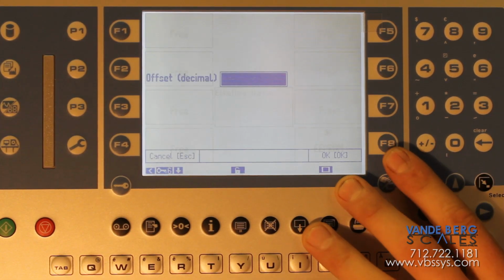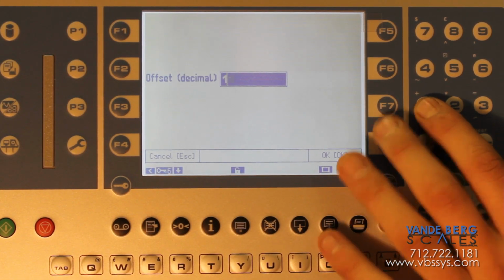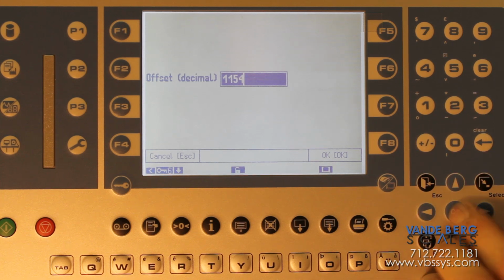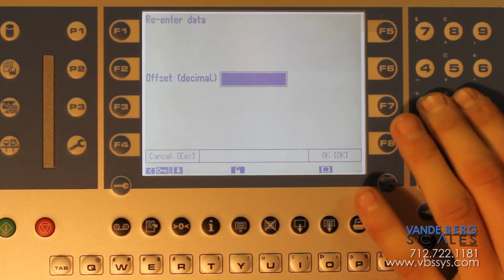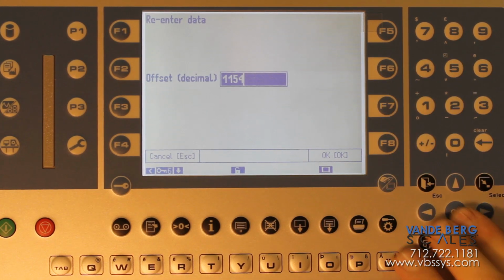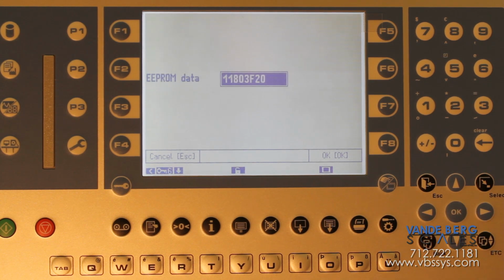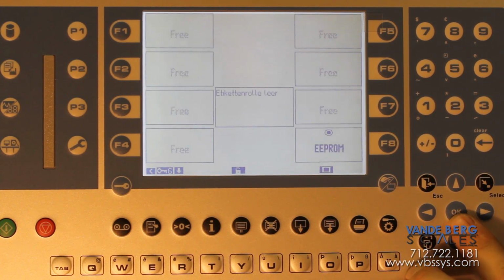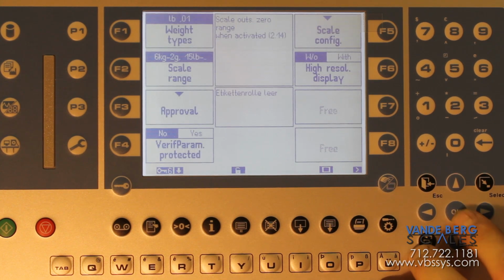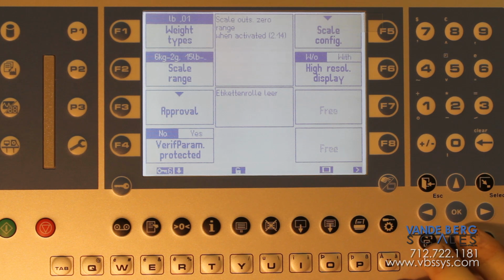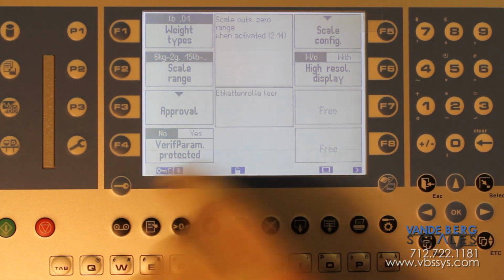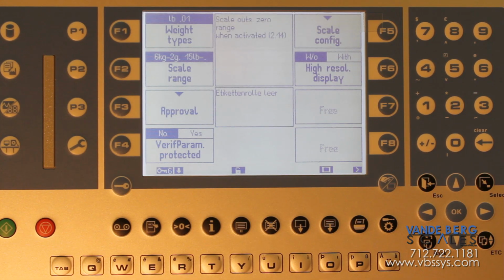We'll set the EEPROM number. That's 1154. Hit OK. It'll ask you to enter it again. Hit OK. The EEPROM data should be 11803F20, which is set right. Hit OK again. The A to D card is now configured. We'll hit the OK button until we get back to the regular mode 6 screen. You can also just press the key and go back to 6 at any time.